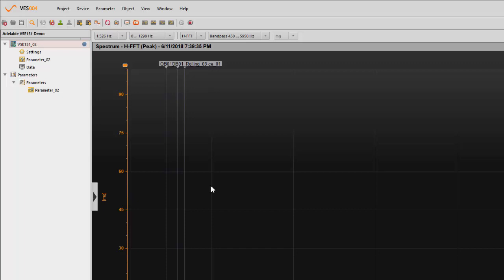Anyway, I've got a good bearing in my unit at the moment. When good bearings are spun and they're in very good condition, they're a perfect rolling element and they will have very little signature, and probably none that are close to what we're looking for at the moment. So I'll show you that. There's a little bit there, but that may not necessarily be the frequency of the bearing. So you can see very low amplitude and nothing actually on our bearing.